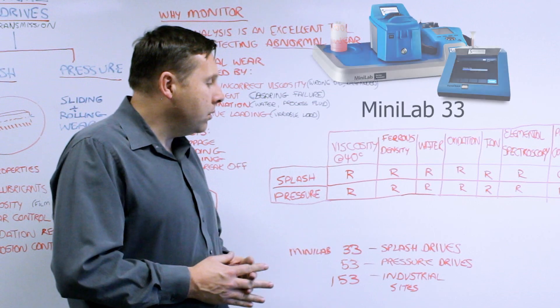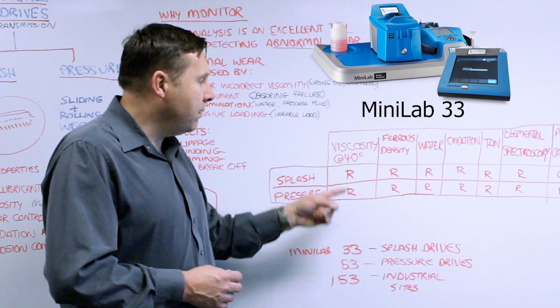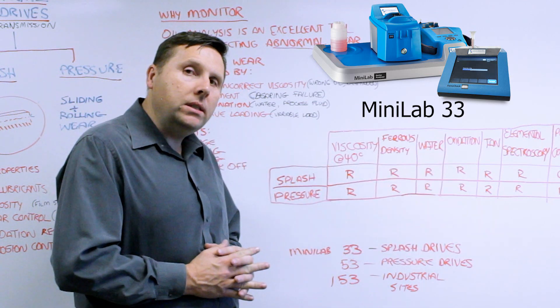The Minilab 33 is a great screening package and it's excellent for splash drives because it's got viscosity, ferrous density, water, oxidation and TAN included.